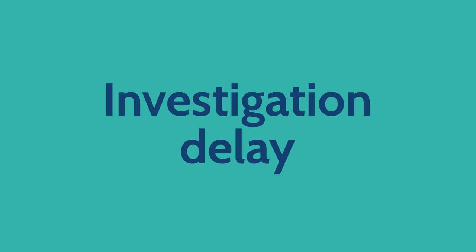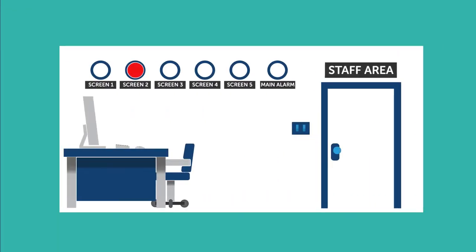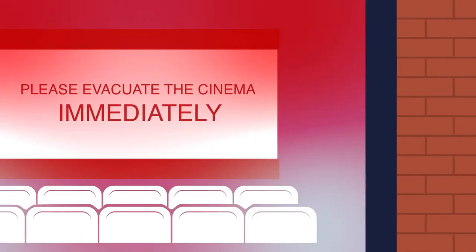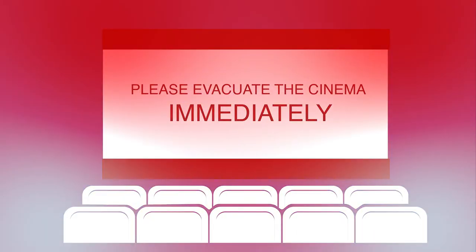Investigation delay: in the cinema, an alarm buzzes in the staff areas which will alert the possibility of a fire, enabling a double check or confirmation of fire by staff before the main alarm triggers and causes a full evacuation.